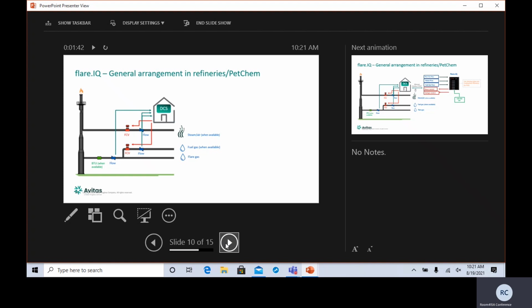So this is a generalized schematic for flares in downstream or petrochemical plants. It's not all; every flare is a little bit unique. The main thing is you have your vent gas line coming in here. Hopefully at this point you have a Panametrics GF868 flare flow meter in place, but after that we just hope we can have an ultrasonic meter as a technology. The BTU front end can be a calorimeter, a GC, or a mass spec.